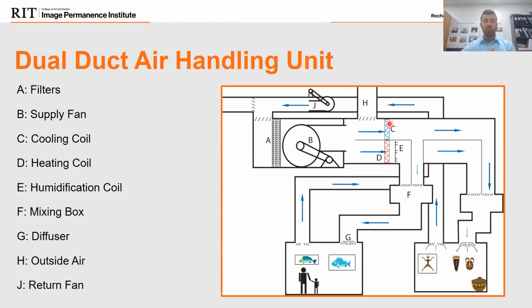And the air is going to either be cooled in one duct, 50% of it can go one way, or 50% of it can go the other. It could be 30-70, depending on the design system. Most of the time it's 50-50. So your air literally splits in two. So now you're going to send 50% cooled air, 50% heated air. And we'll use this room as an example. I'm trying to make a condition here. They're going to regulate the doors on these dampers, the doors on this box. So it's going to mix the amount of each air, cooled and heated air, to achieve 72 for here and 60 degrees for here to satisfy that. Again, then I have to return that air back and do this process over again. So mixing conditions is also very inefficient. Dehumidifying with these units is very hard to do because you're only dehumidifying 50% of the air. You're getting one swipe at 50% of the air as it goes.